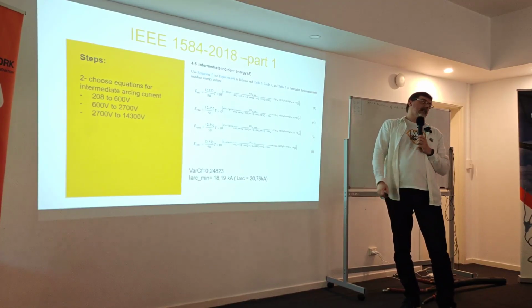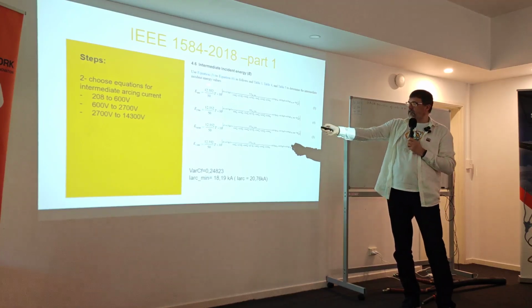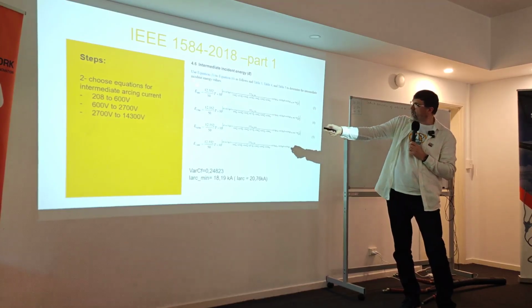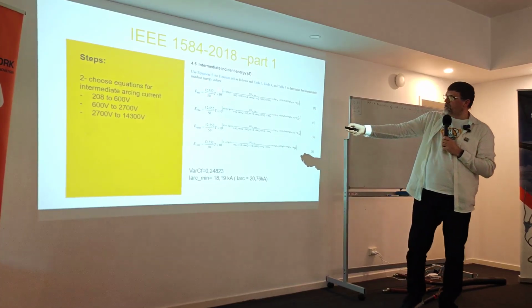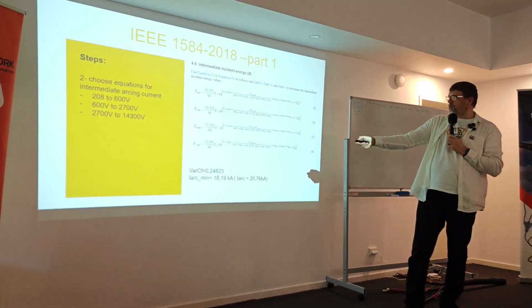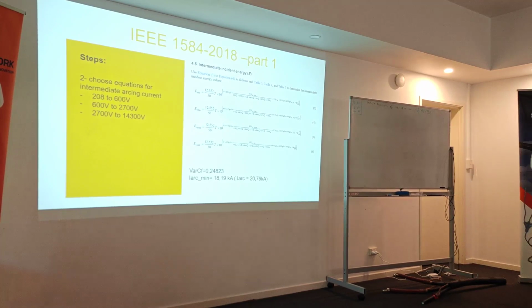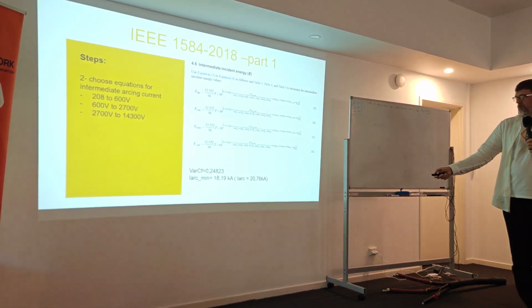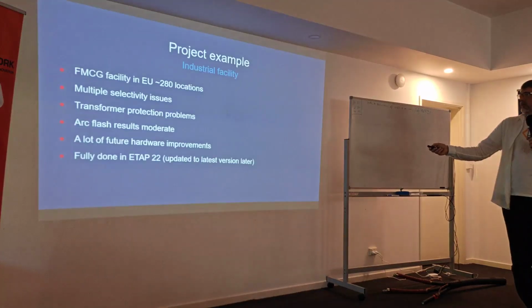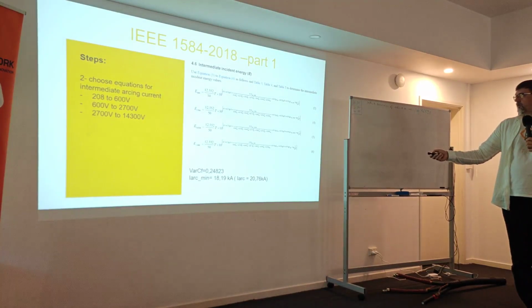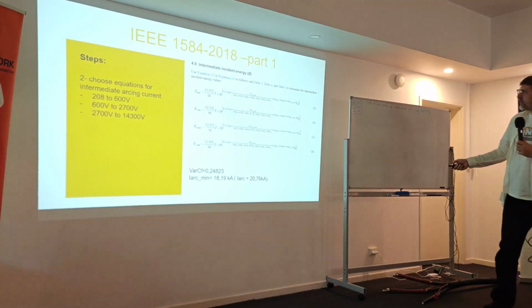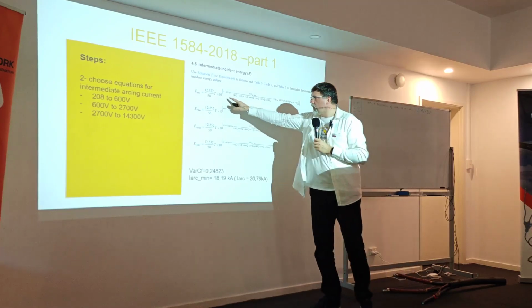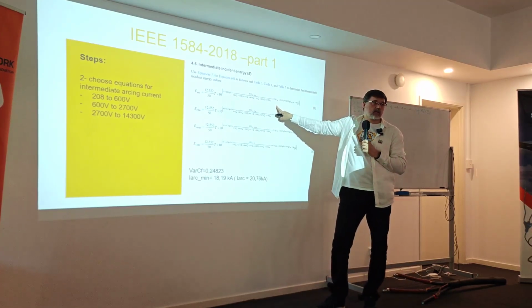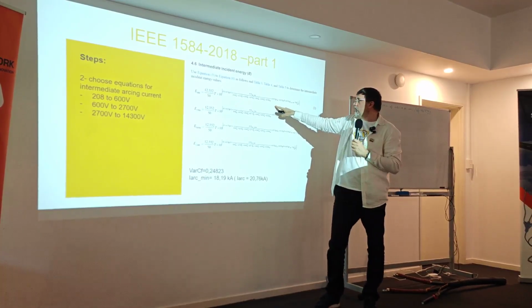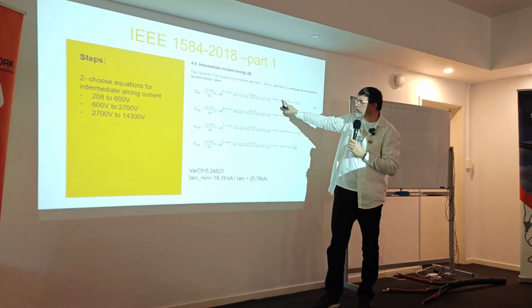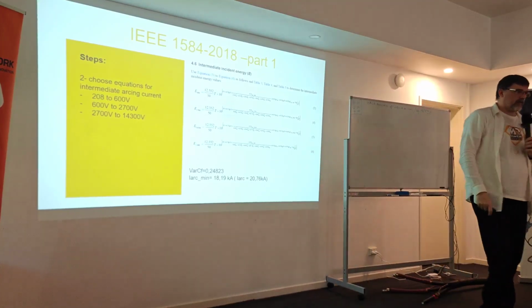And then we go to the point where we can finally calculate the first energy. I specifically choose this one, again 13 coefficients, because here we have to calculate 1, 2, and then recalculate in between. So we have 415 volts, we calculate it. I have a minimum arc, I have a normal arc, I have this var coefficient as well. And where's my calculation? Did I stop here? Because it was 20 something calories. When you put everything in, there's the same coefficient factor that I used in the previous one. For this, there is one table that you use from the VCB, and there are additional coefficient factors for K13, which I have, I think, in Excel.